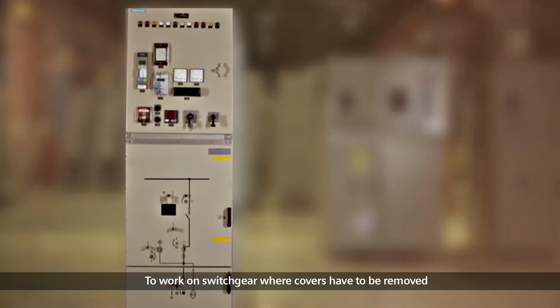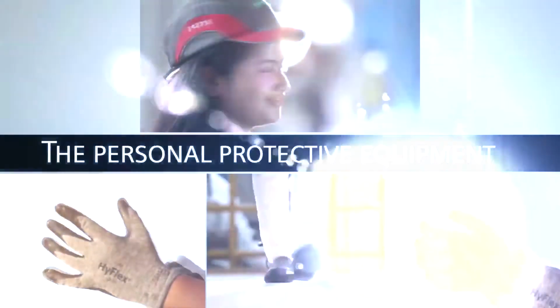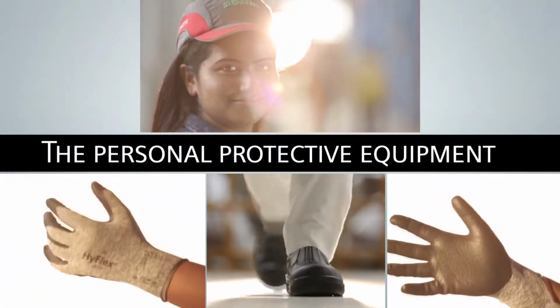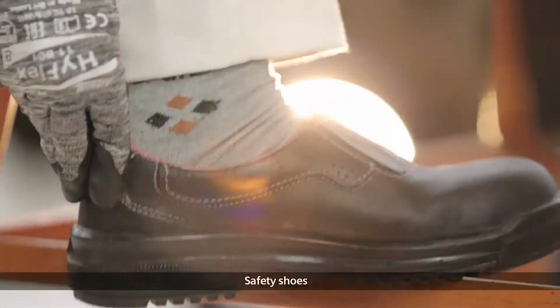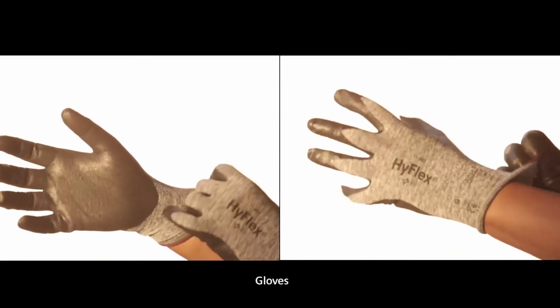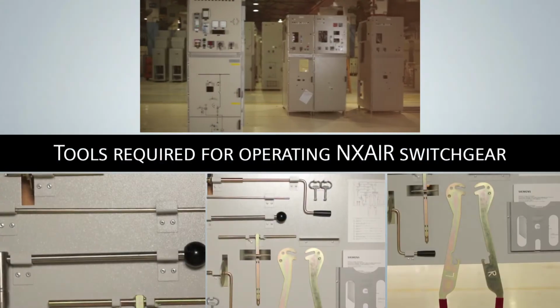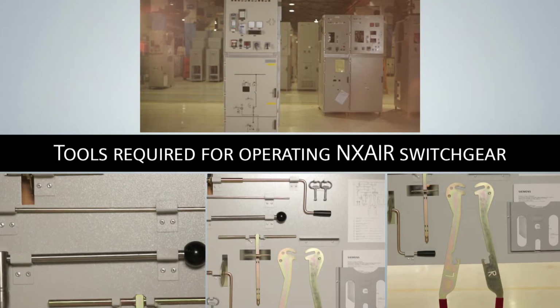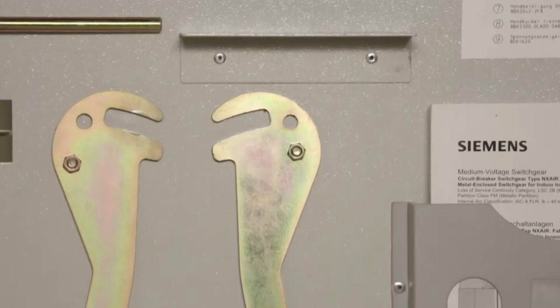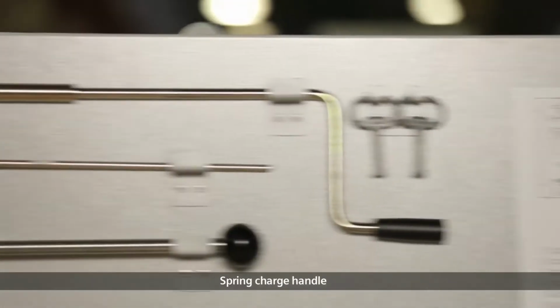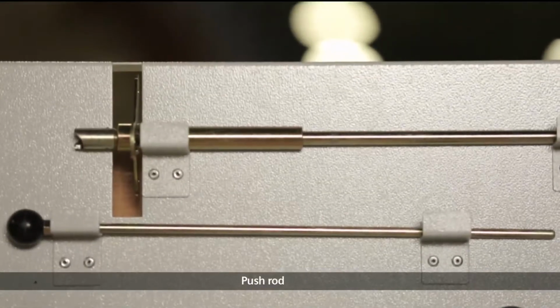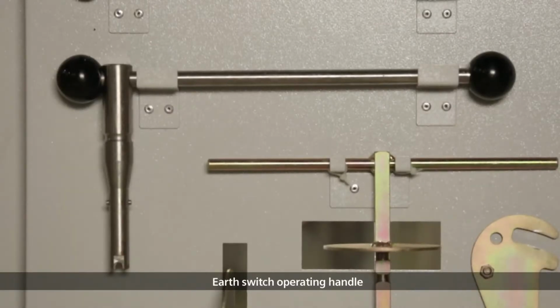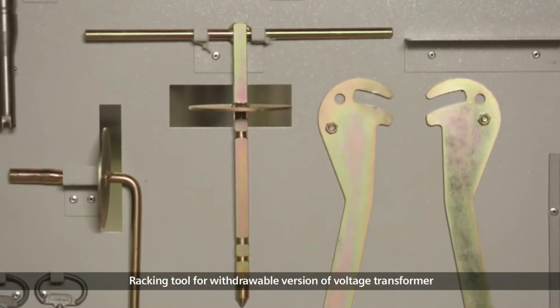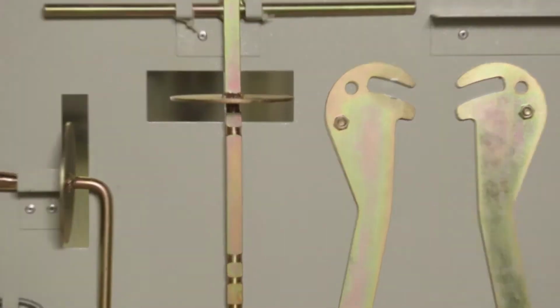To work on switchgear where covers have to be removed, personal protective equipment has to be worn, which are safety shoes, gloves, helmet. Tools required for operating NX Air switchgear are shutter lifters, double bit key, racking handle, spring charge handle, push rod, earth switch operating handle, racking tool for withdrawable version of voltage transformer.